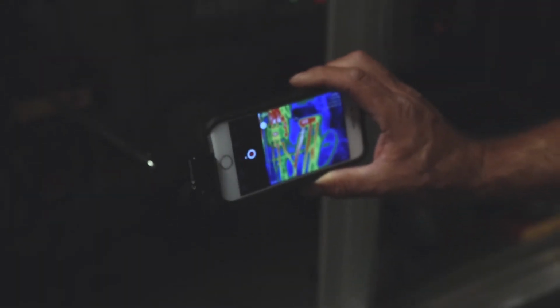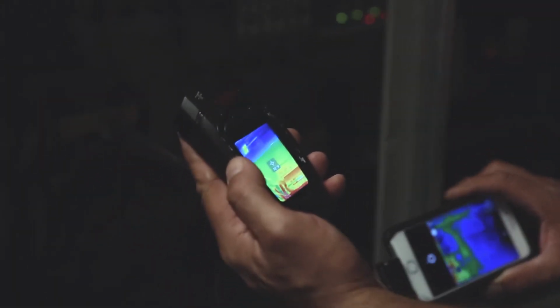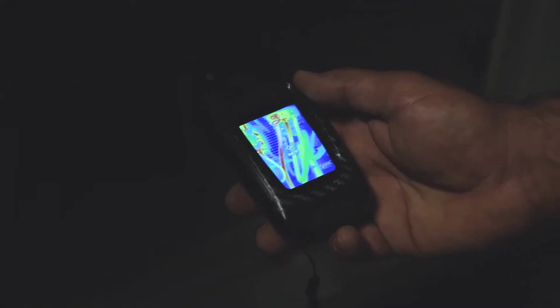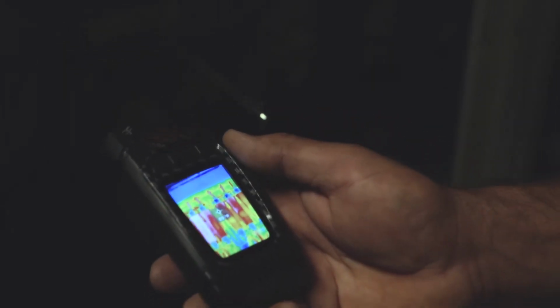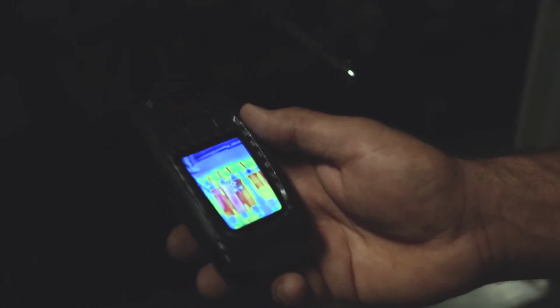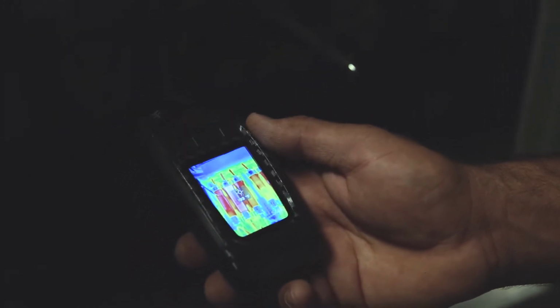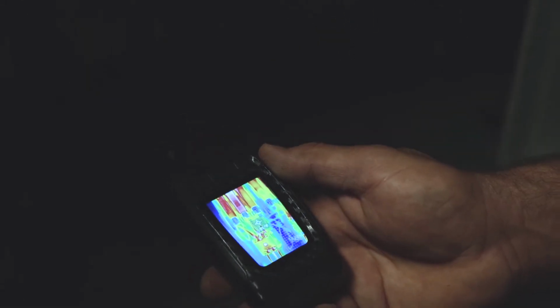I'm going to shoot it with the handheld device also. So you can definitely see the left wire right there. Shows a lot hotter than the others. And we wouldn't know that until that wire burned up. Absolutely, you'll never know. Look at that fuse in the center there. Looks like it's cooking, which indicates maybe there's something going on there. We have a loose connection here.